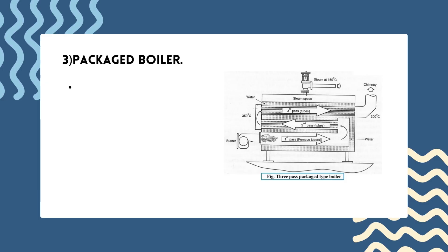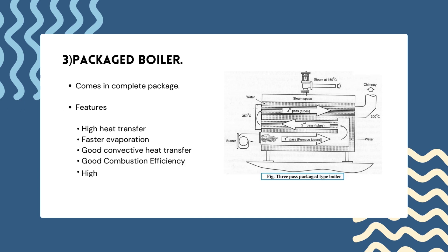The packaged boiler is so called because it comes as a complete package once delivered to a site. It requires only the steam and water pipework, fuel supply and electrical connections to become operational. Packaged boilers are generally of a shell type with a fire tube design to achieve high heat transfer rates by both radiation and convection. They are used for heating and as steam generators for small power purposes such as self-powered industrial plants, but cannot be used for large-scale power plants due to their size and lack of efficiency.